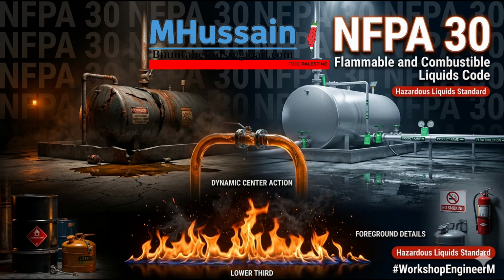To contextualize, 0.60 GPM per square foot. That is a torrential, localized monsoon. Right. It requires massive fire pumps, huge piping diameters, and an enormous municipal water supply. It's a highly aggressive tactic to rapidly cool the ambient temperature in the steel containers so they don't boil. But, and here's the crucial caveat, when you're dealing with massive volumes of ignitable liquids, dumping thousands of gallons of water is sometimes the absolute worst thing you can possibly do.